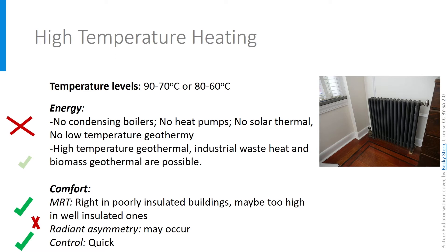The problem with high temperature heating is that it cannot be achieved when using renewable energy. To achieve a supply temperature of 90, there is almost only one solution, and that is to use a boiler using fossil fuel, or at best biomass or biogas. With such a high temperature, the boiler cannot work in condensing mode, and heat pumps, solar systems, and low temperature geothermal energy are excluded. So that is not really future proof, unless a high temperature geothermal plant is available, or industrial waste heat that could produce heat at 90 or 80 degrees. Burning biomass is possible too, however there are doubts about the sustainability of biomass at large scale.